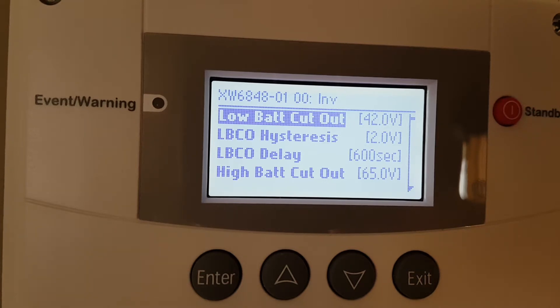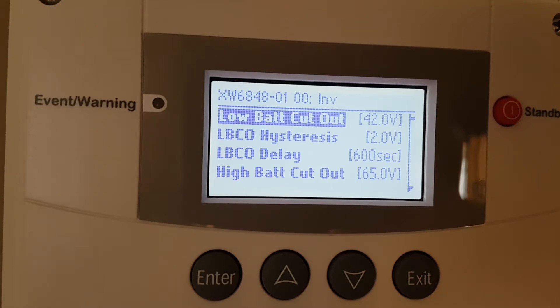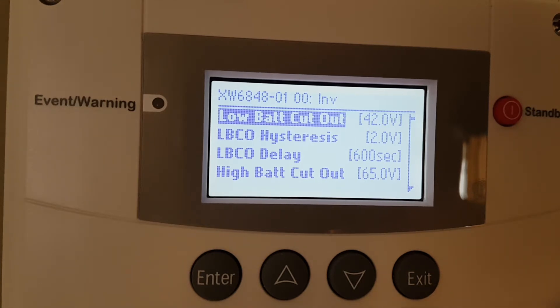I have a special battery and my low battery cutout delay is 600 seconds. The reason why it's that long is: let's say I put a really big load on the system and it's so big that the generator needs to start. I want that delay to be long enough so that by the time the generator starts, the inverter is still on, and by the time the generator warms up and connects, the inverter is still on. You need quite a few minutes when you consider how a diesel engine works — the glow plugs, the warm-up period, and everything that needs to qualify before it connects.